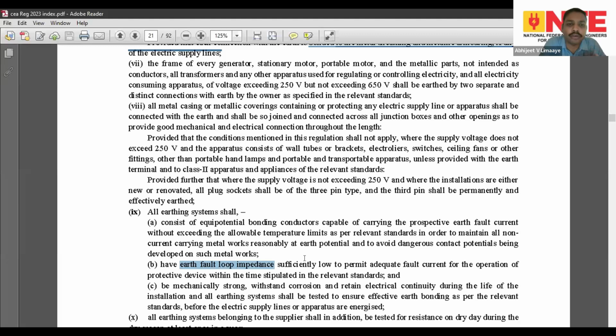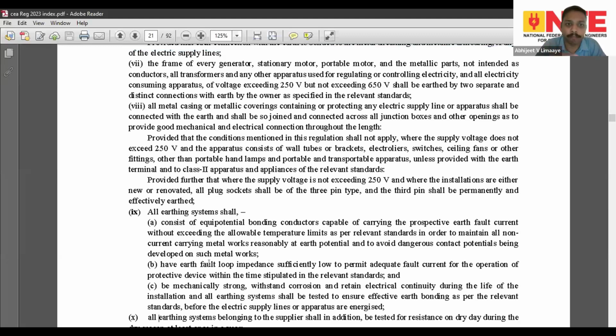Another aspect we need to understand about fault loop impedance is that just by knowing the value, we cannot attribute it to a particular value, let's say 5 ohm or 1 ohm or maybe less or more than that. Fault loop impedance is a value which needs to be measured, and your protection system needs to be calibrated for an automatic disconnection.